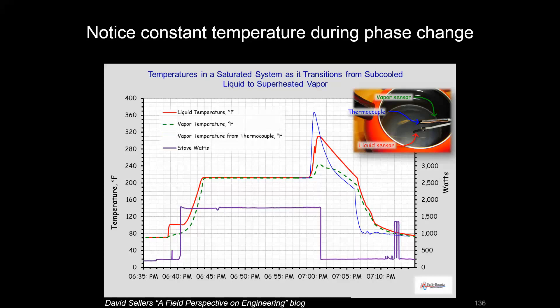There's still energy going into that water, the stove's still on, but it's sitting at that temperature. And that's a very key point to talk about when we're examining saturated systems like steam and different refrigerant systems. In order to accomplish a phase change, it takes energy. It's going to sit at that temperature until it completes its phase change. And that's very key in how we use those systems to manage loads and pass loads around from one system to the next.